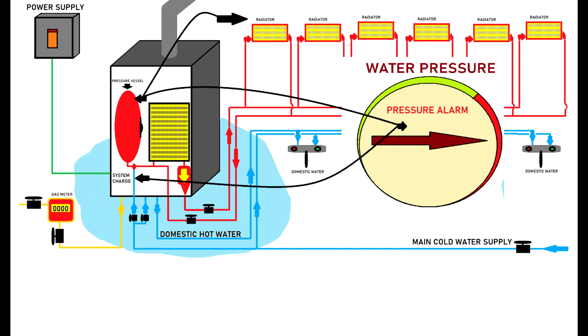Finally, when you charge the system with water, you will have a manual charge where you have to open two taps to allow the water to fill your installation. When you lose a little bit of water, if you charge it too much, then when the water heats up, the pressure will go into the red. So there are four main things which can happen. Number one, you can charge the system too much when it's cold, and when it heats up, the pressure will exceed, because the pressure vessel won't be able to take such a big volume. Two, you have a large installation, larger than the pressure vessel can handle. Three, you have a faulty, contaminated heat exchanger, and because of that the heating in the heat exchanger is very aggressive. You'll create some steam mixed with water, you'll hear some hammer knocks inside, and that will increase the pressure.